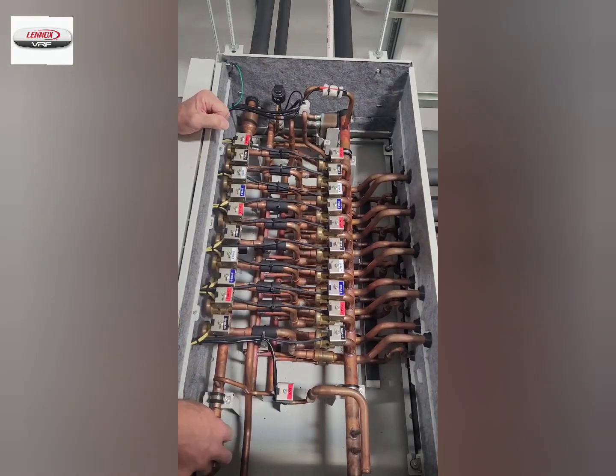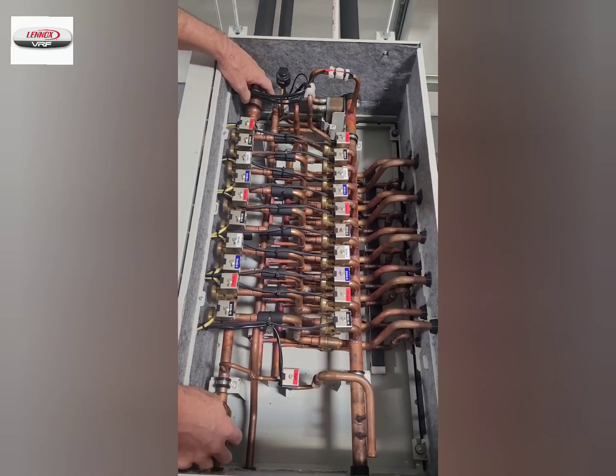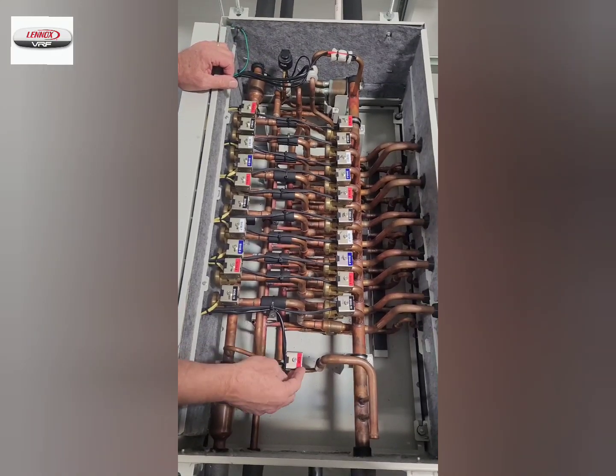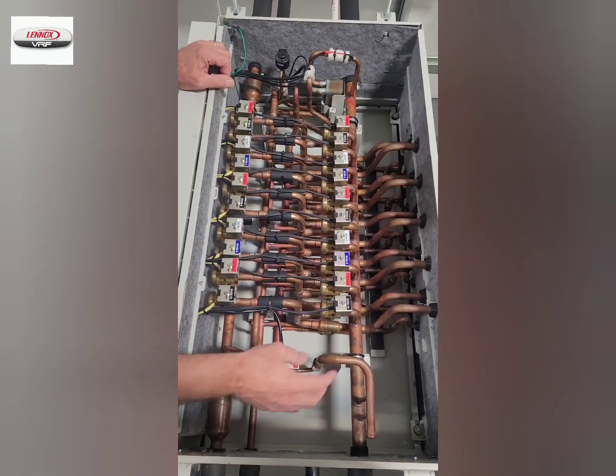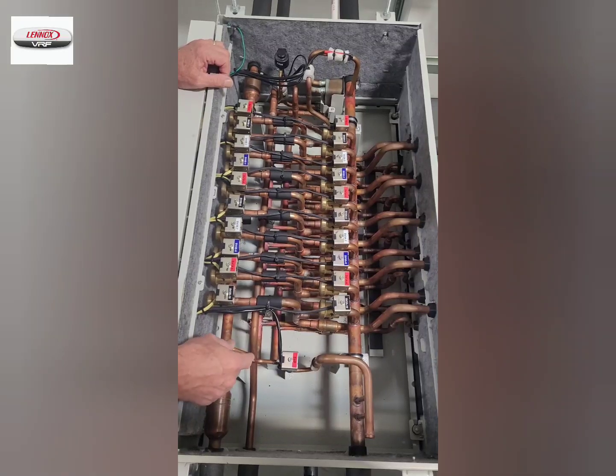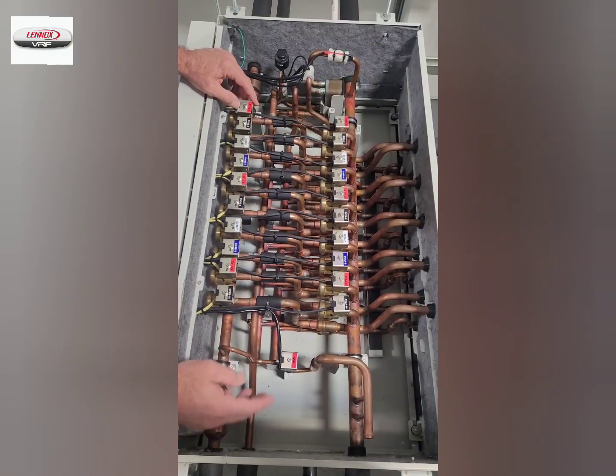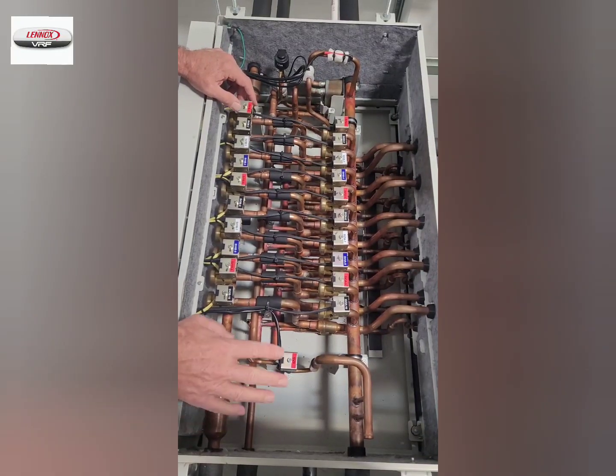You also see some strainers on the hot gas line. They are not filter dryers, they are simply strainers. There is a solenoid valve here, which equalizes the pressure from the hot gas line to the suction line every time the unit changes over from heating to cooling or vice versa.